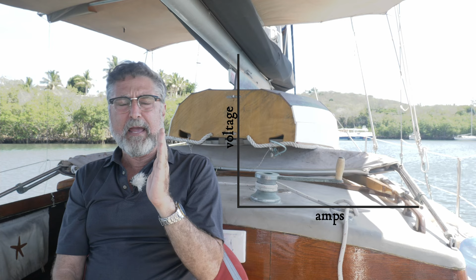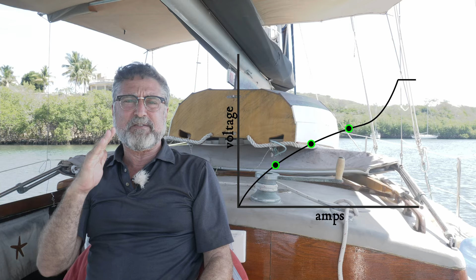What you'd find is you charge them at a known amount of amps. You charge them at 20 amps, let's say, and for that 20 amps you keep charging until the voltage comes up to a certain level. When it hits that level, you stop charging, you're done. If you charge at more amps, you actually come to a higher voltage before you're done. And if you charged at a very low rate, you'd find the voltage is actually quite low when they're fully charged.